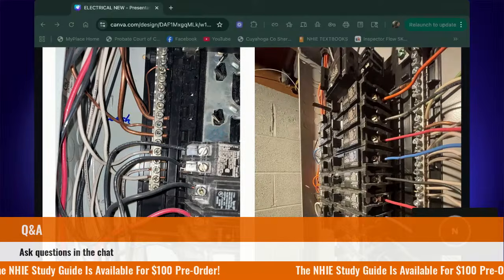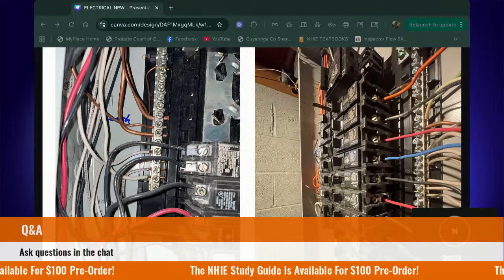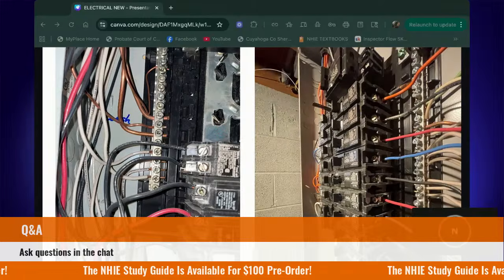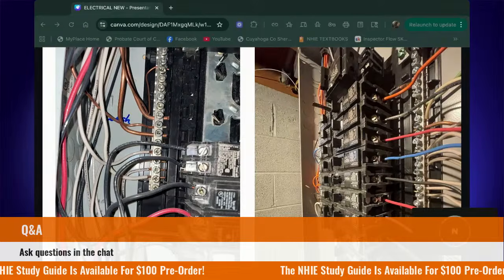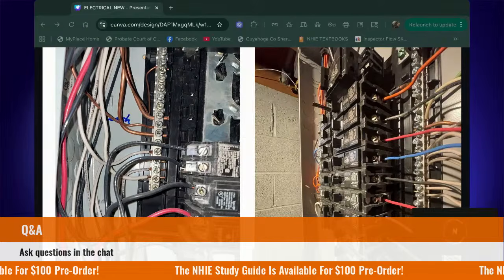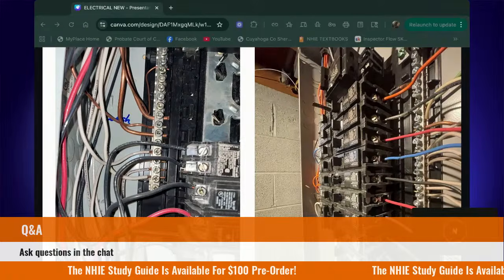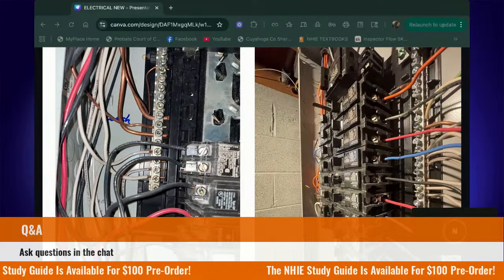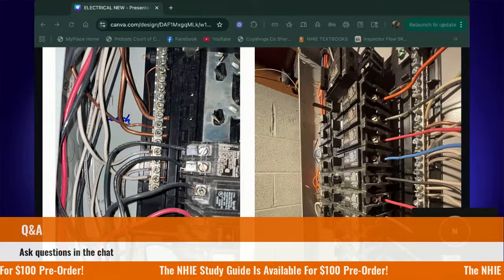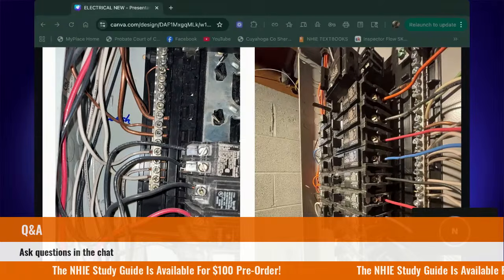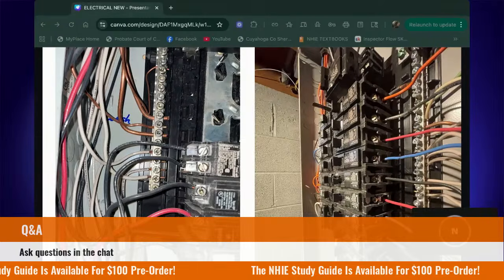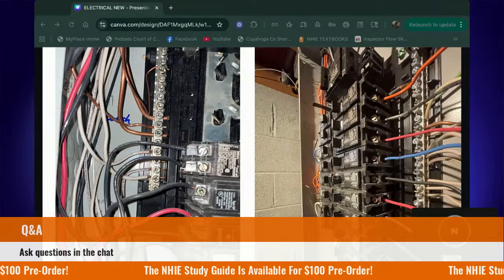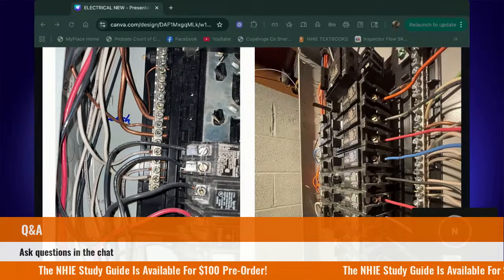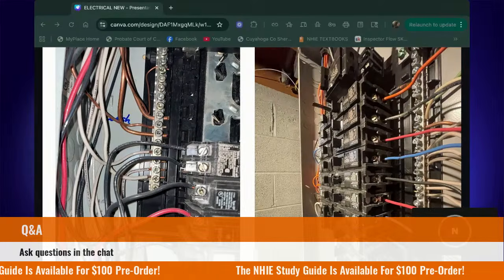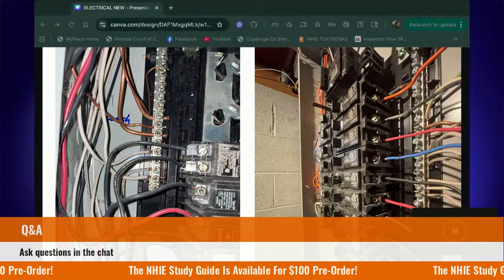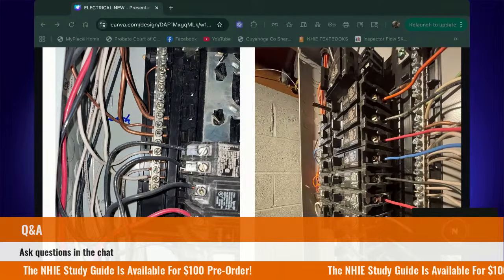In our main panel, can the neutrals and the grounds terminate on the same bus bar? Yay or nay? Yes. Why? Because they're both grounds. I think no, because it's the ground carrying the current, and the neutral is carrying the current to a certain place. The neutral is carrying it back to the source. In a normal operating system, will my ground wire be carrying current? No. Why not?